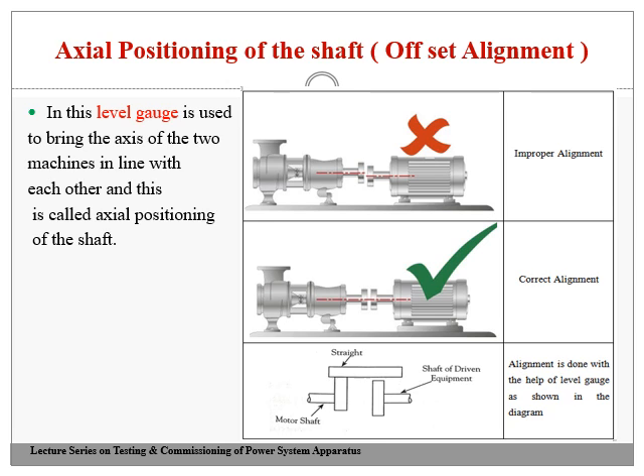What should the proper alignment be? In the incorrect case, the axis of one shaft and the axis of the other are totally different. After making the alignment using offset alignment, or axial positioning of the shaft, you can see that the axes of the shafts are in line with each other. Hence, I can couple it properly now. This is done with the level gauge. You can see in this figure that this one is upper and this one is at the bottom. You can have a slight gap here.